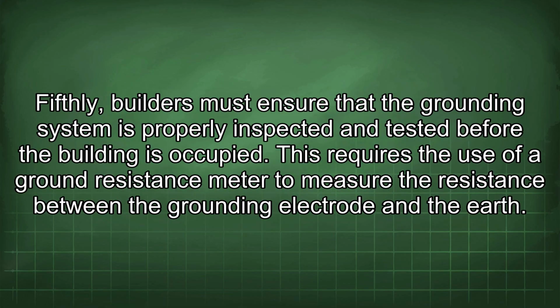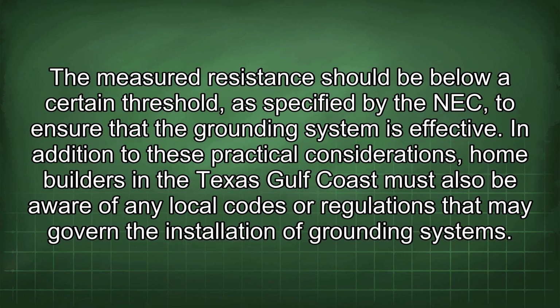Fifthly, builders must ensure that the grounding system is properly inspected and tested before the building is occupied. This requires the use of a ground resistance meter to measure the resistance between the grounding electrode and the earth. The measured resistance should be below a certain threshold, as specified by the NEC, to ensure that the grounding system is effective.